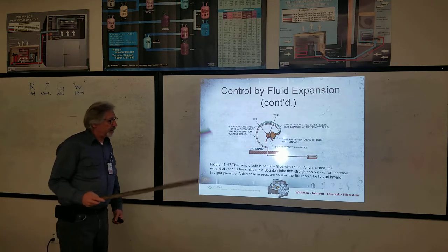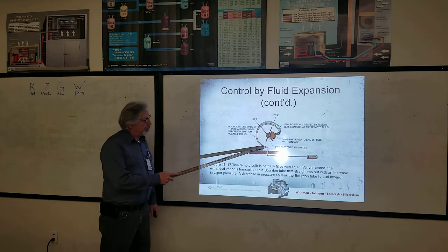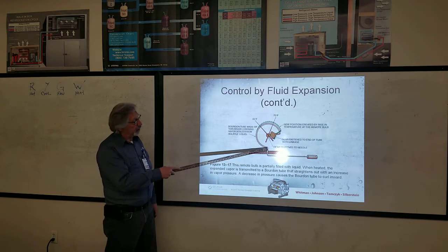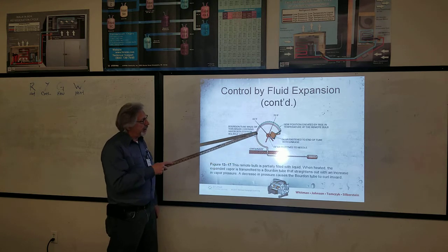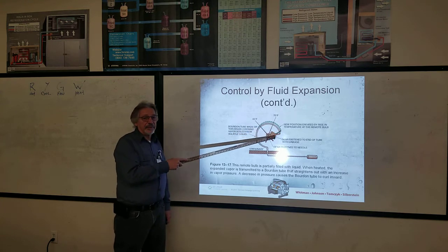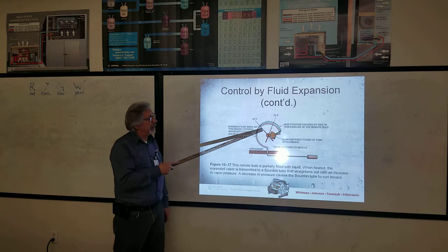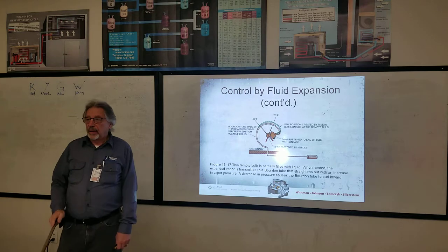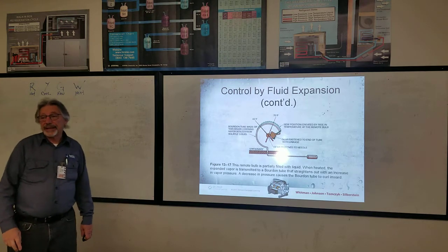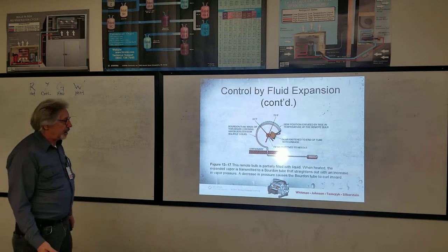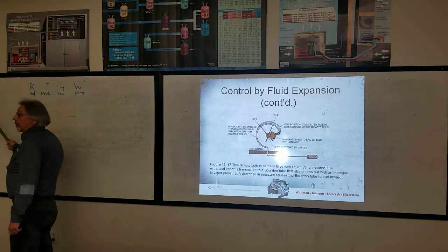And we also have the bourdon tube. This bourdon tube is hooked to a volatile fluid, as you can see, and it looks like it's reading temperature. As the pressure increases, this tube starts to straighten out. As it straightens out, it pivots and moves a little needle indicating what temperature it is according to that pressure. So it's kind of like a gauge. It is. This is what's in our gauges, the bourdon tube.